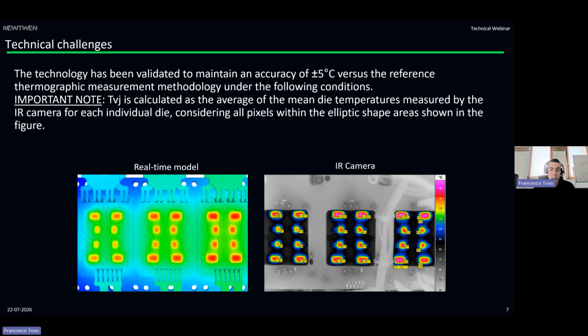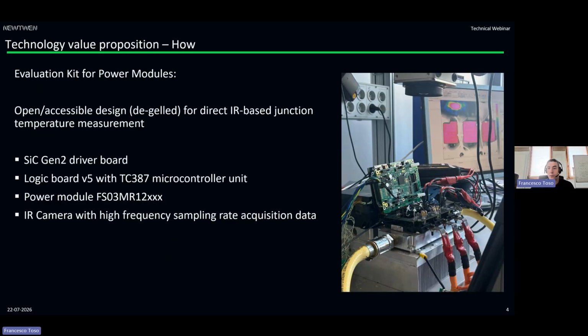Given that, it's important to have a standard procedure for collecting junction temperature data to establish ground truth. Of course, in production, once your inverter is fully built, you don't have this kind of setup — you can only rely on current measurement, voltages, polydiodes, or NTCs, whatever thermal sensor technology the power module supplier uses.